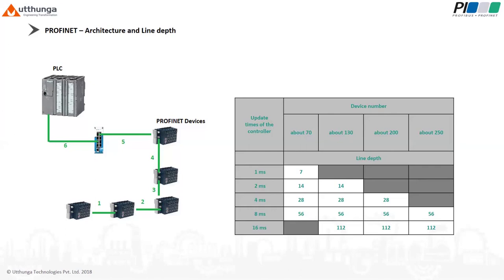And Profibus is, as we say, half duplex, since it is two-wire communication. It's a differential voltage communication happening in Profibus, while PROFINET, as we studied right now, is full duplex with four-wire communication. That's actually a glimpse of what we studied right now. It's the difference between Profibus and PROFINET.